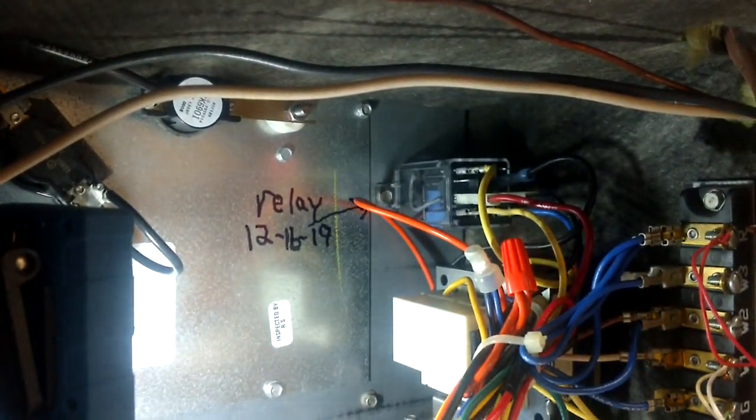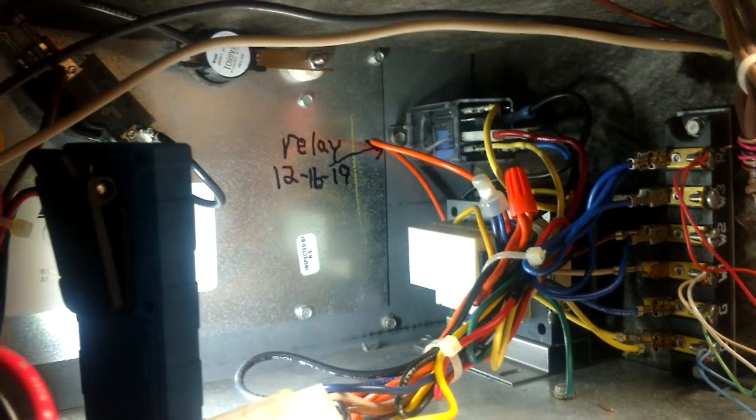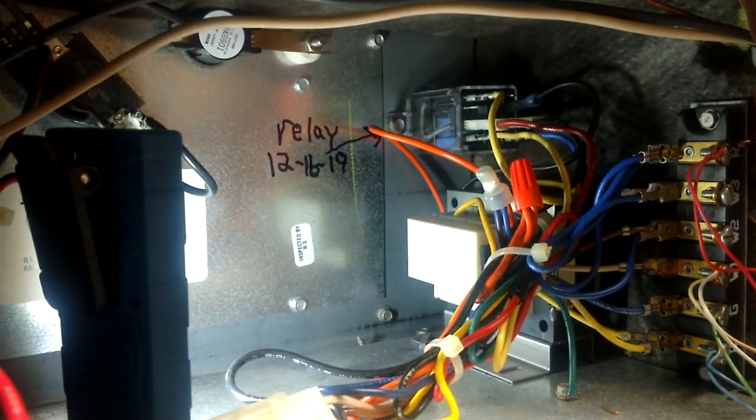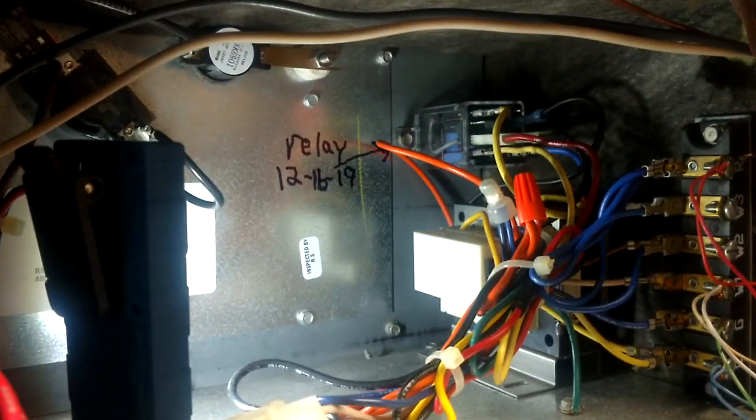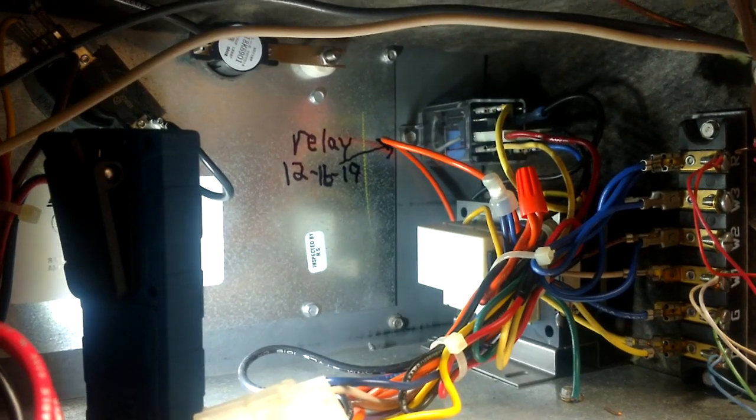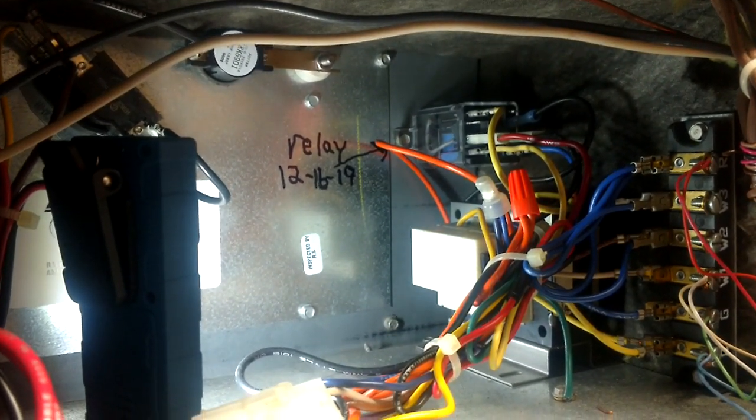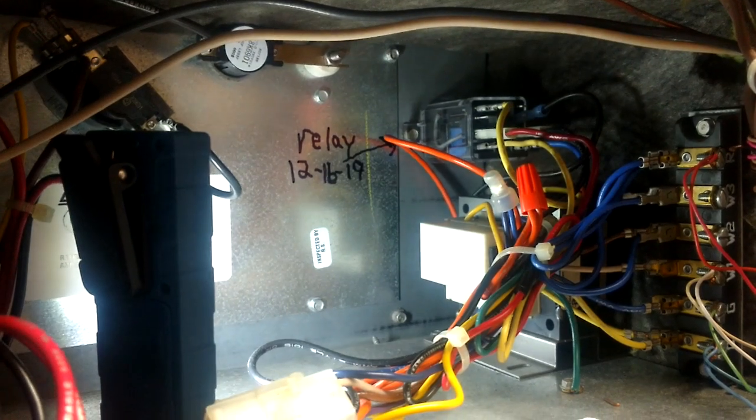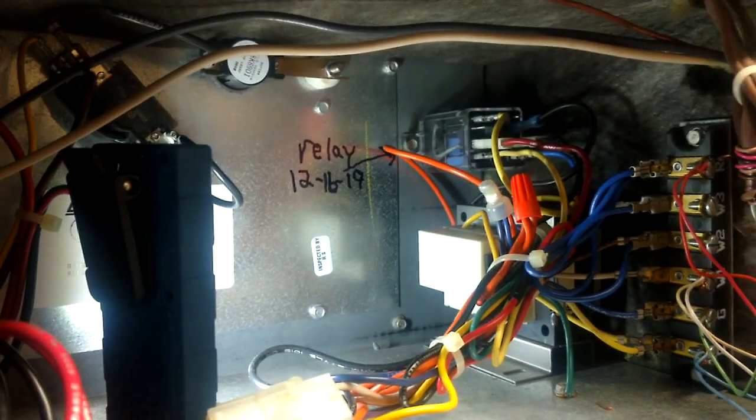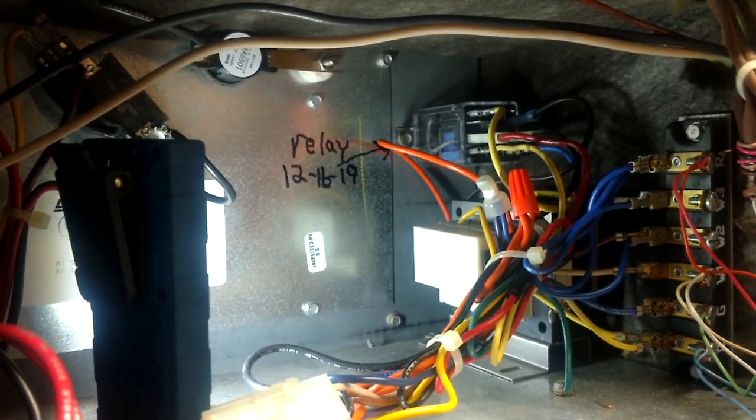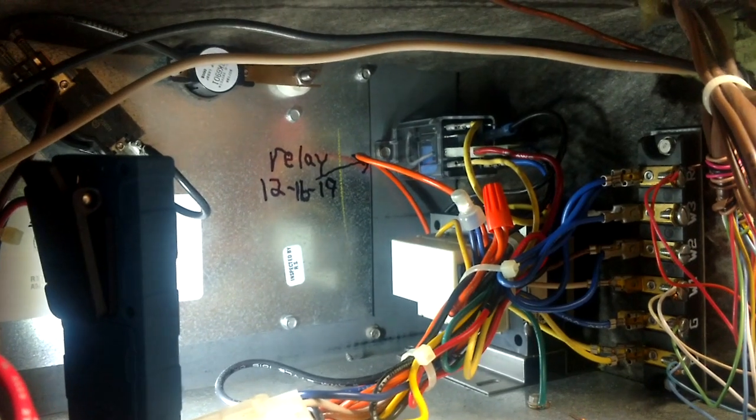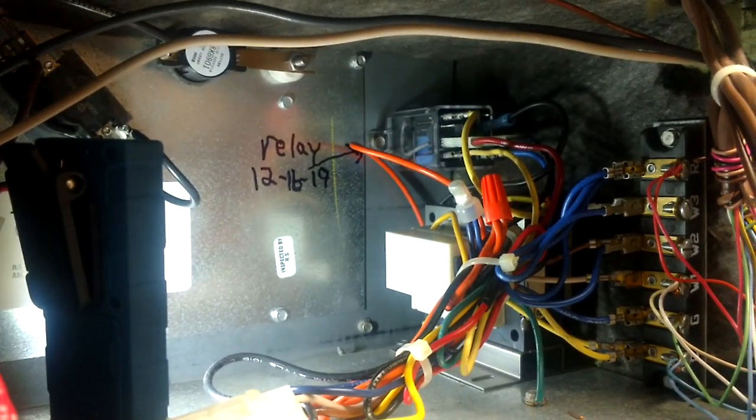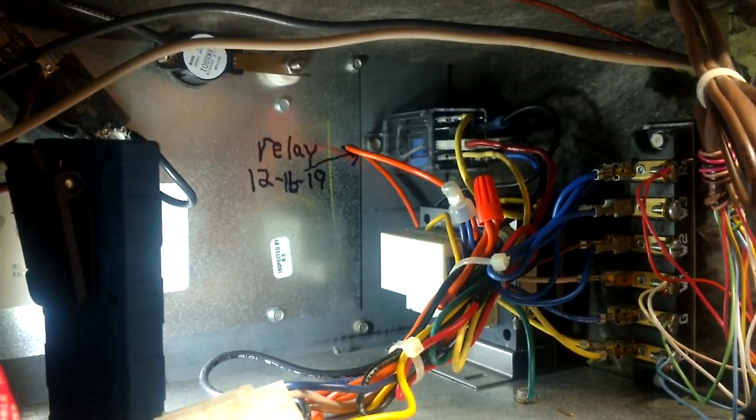All right, you guys. The only other thing I can recommend on those and every relay, and man, I've made the mistake myself. Make sure you grab one with a 24 volt relay. Every now and then you'll get one with a 240, a high voltage pull on the relay, and they'll get mixed in with your low voltage coils. And you'll go through all this trouble putting the thing on.